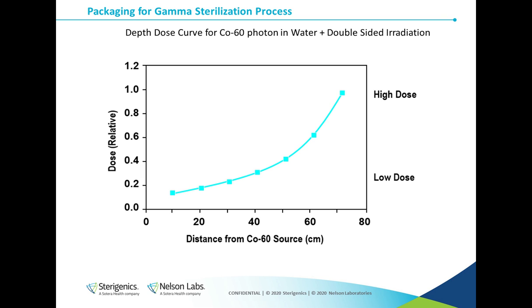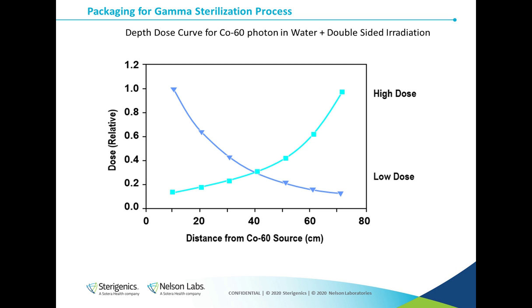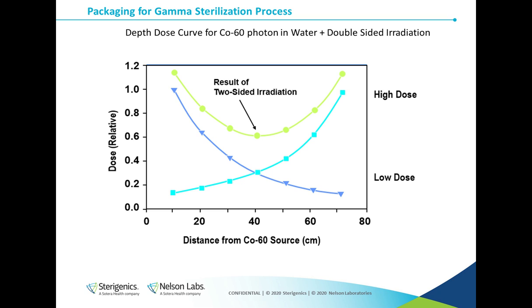We typically irradiate the material from two sides in gamma processing. If we irradiate the material from a single side, this is what the dose profile on this slide would look like through the irradiation container: a high dose on the surface, the right side of the graph, and lower doses as we penetrate through to the left side of the irradiation container. If we then irradiate the container from the other side, we would have the opposite dose distribution, a high dose on the left side and lower doses as we penetrate through to the right side.